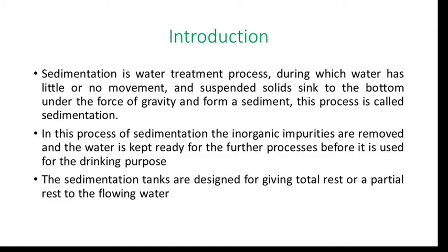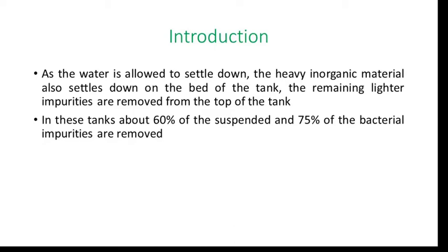Okay, so basically, this process is nothing but allowing the solids to settle by gravity force into a tank. That tank is called a sedimentation tank or settling tank, either a rectangular tank or a circular tank. The settlement of inorganic impurities from water into that tank is called the sedimentation process. It removes up to 60% of suspended solids and 75% of bacterial impurities.